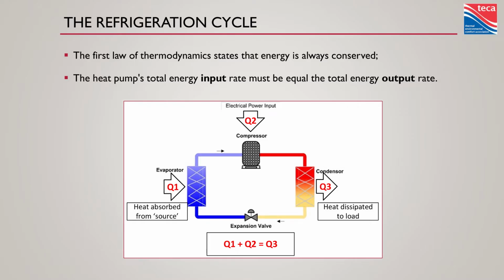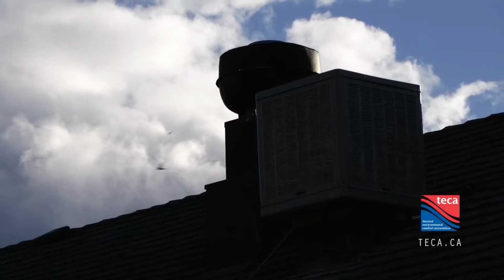When we measure heat pump efficiencies, we're not talking about percentages of 100% like we do with, say, a gas appliance. We can never get 100% of the potential energy out of that fuel. But in a heat pump, it's always in the positive in percentages. We measure it in COP, or coefficient of performance. So a COP of 1 is 100% efficient. One unit of energy consumed delivers one same unit of energy. So if we use kilowatts, you buy a kilowatt from hydro and you get a kilowatt of heat, 3,412 BTUs.